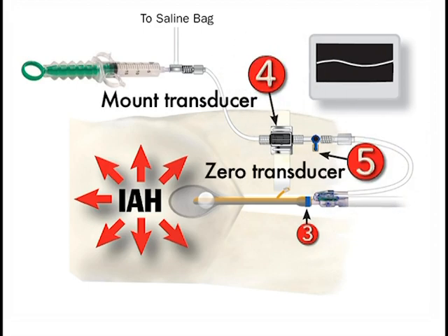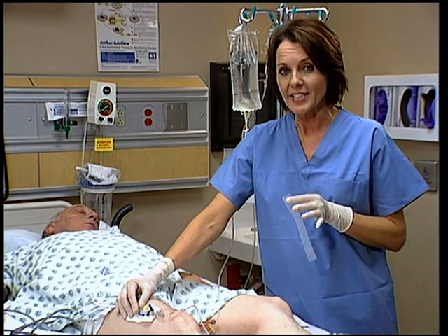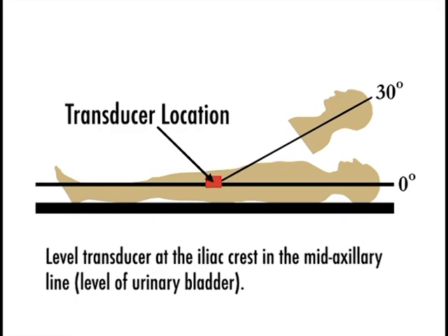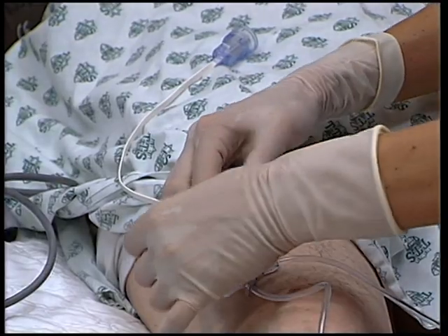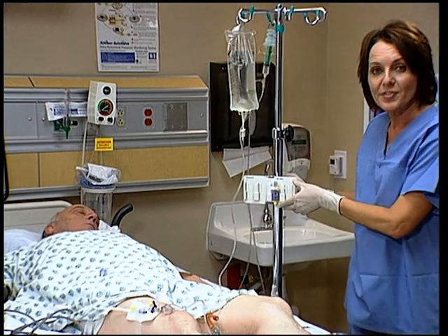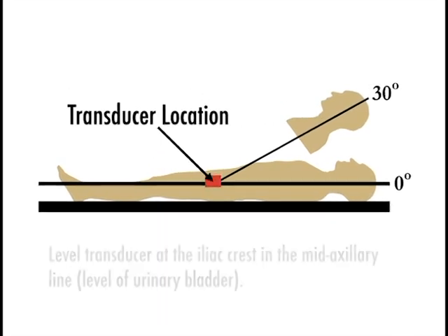Once you've attached the AbVisor valve to the urinary drain system, you cannot disconnect it without risk of damaging it. Now mount the pressure transducer to the patient or the pole. For patient mounting, place a 4x4 on the thigh at the level of the iliac crest in the mid-axillary line, and tape the transducer in place. If you choose to pole mount the transducer, place it in your pole mount bracket and adjust the bracket to the level of the iliac crest in the mid-axillary line.